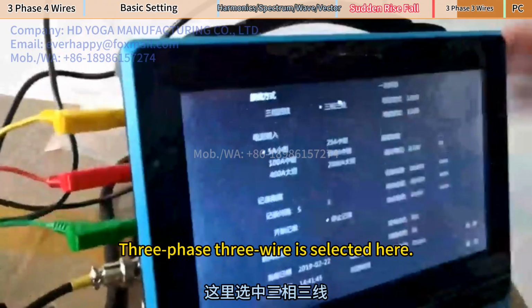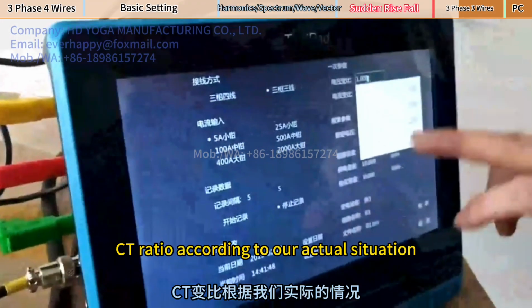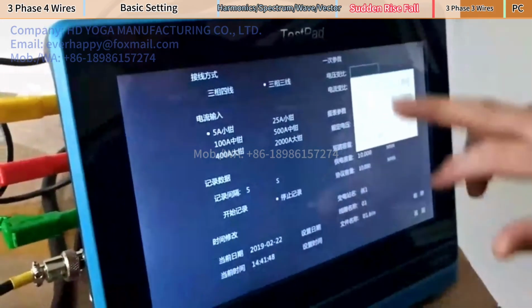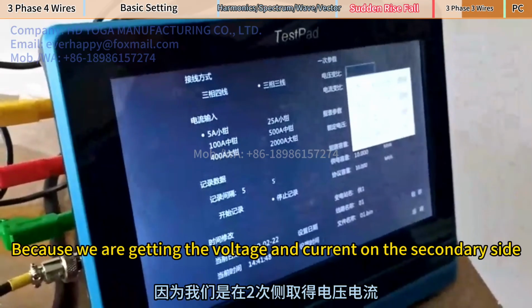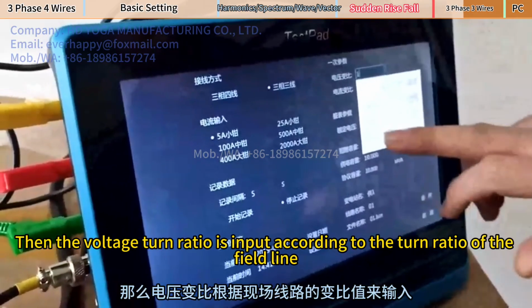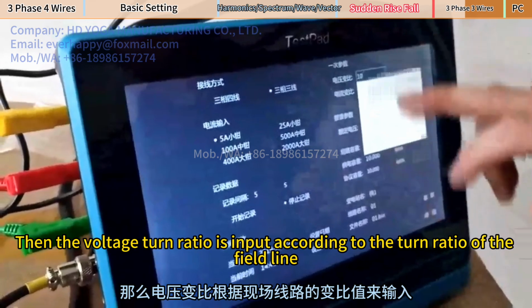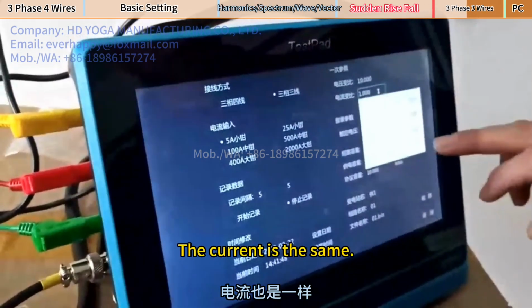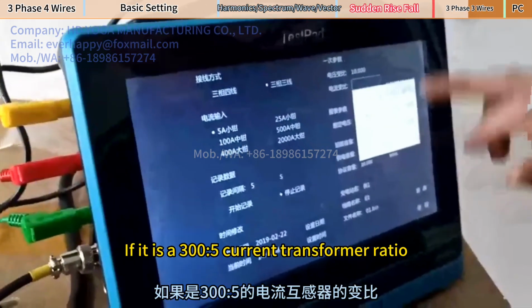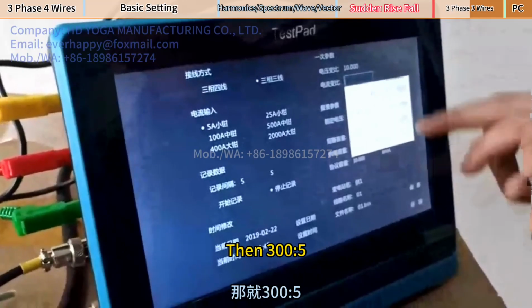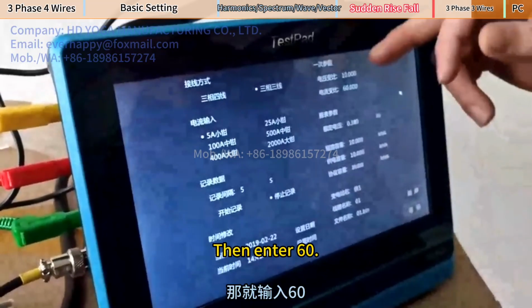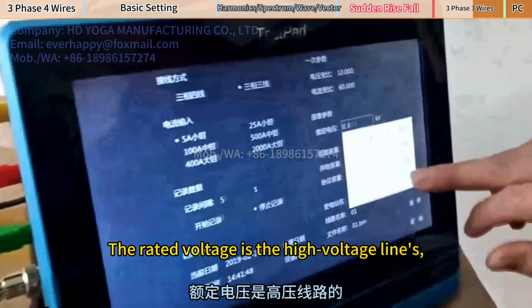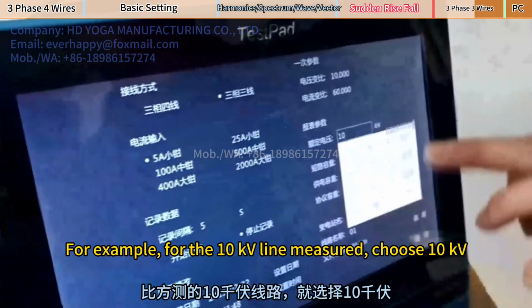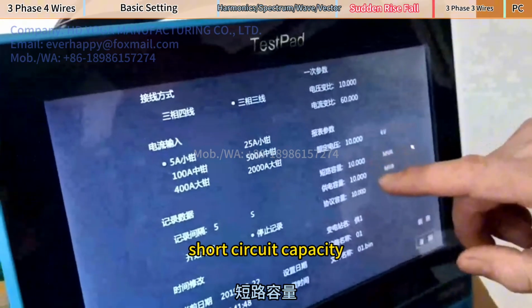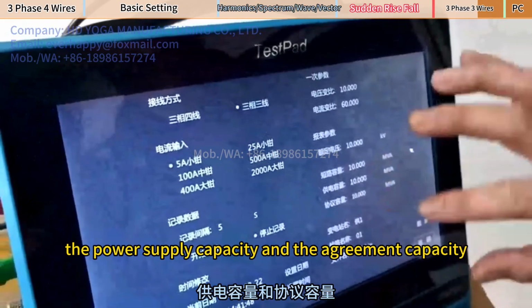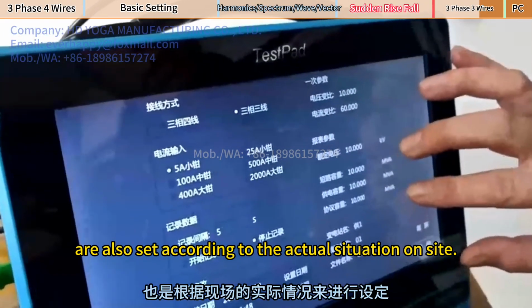3-phase 3 wire is selected here. Then PT turn ratio, CT ratio according to our actual situation. Because we are getting the voltage and current on the secondary side, then the voltage turn ratio is input according to the turn ratio of the field line. The current is the same. If it is a 300:5 current transformer ratio, then 300:5, then enter 60. The rated voltage is the high voltage lines. For example, for the 10 kV line measured, choose 10 kV. Short circuit capacity, the power supply capacity and the agreement capacity are also set according to the actual situation on site.